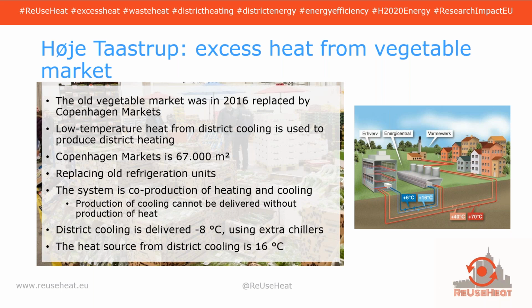So it's a system that co-produces heating for the district heating network and cooling for the market, where the cooling cannot be delivered without the production of heat. So it's a great utilization of the synergy between industrial cooling and district heating. As you can see on the figure here to the right, the district heating network operates with standard temperatures of 70 and 40 degrees, while on the cold side, temperature is delivered at around 6 degrees, but actually cooled to -8 degrees using some extra chillers, and then returned to the district heating at 16 degrees.